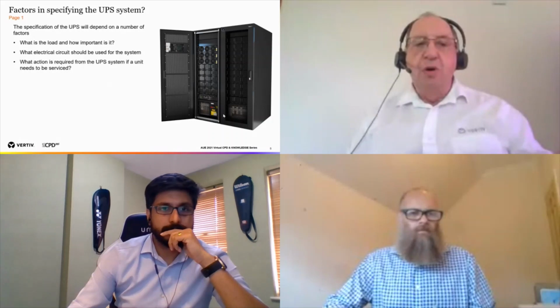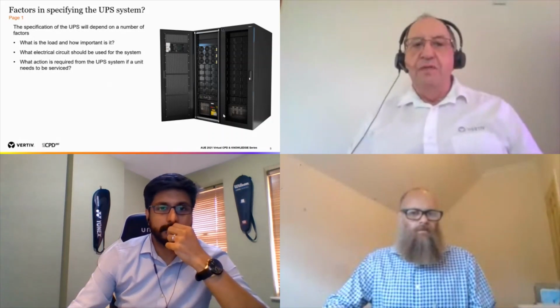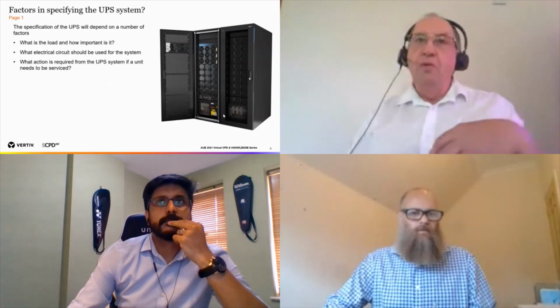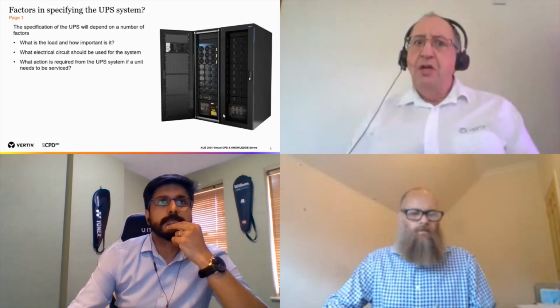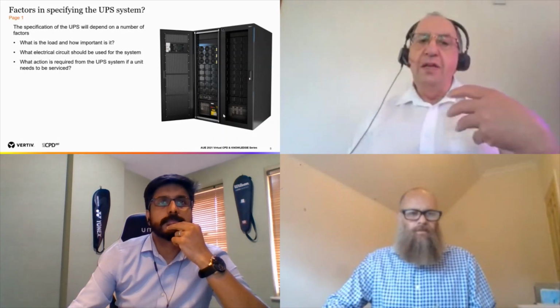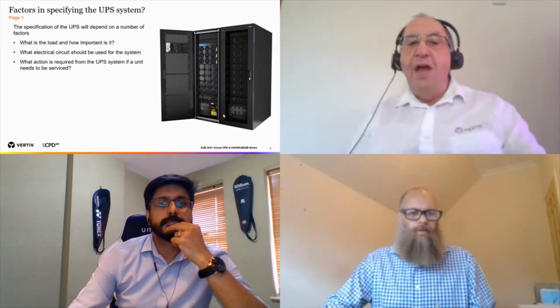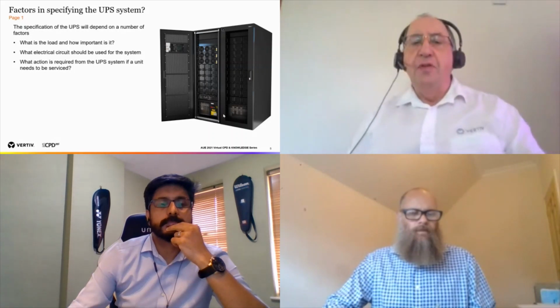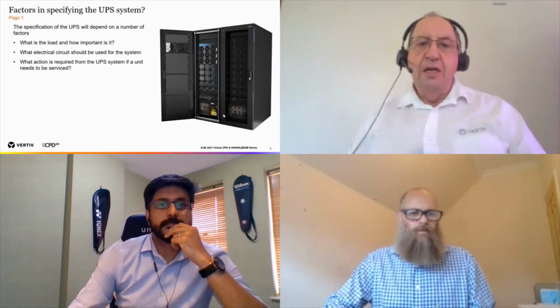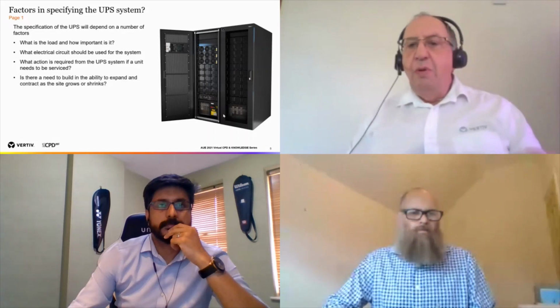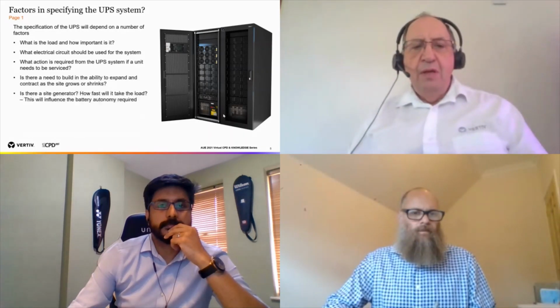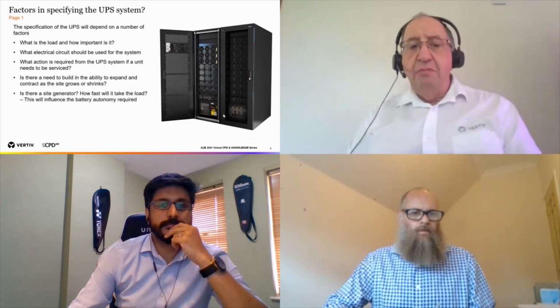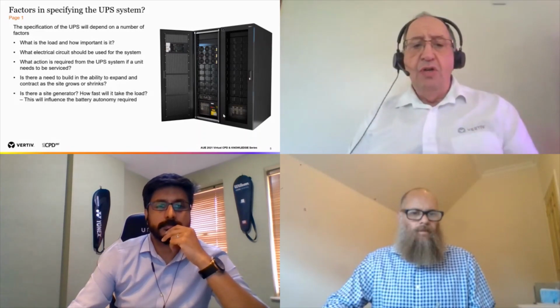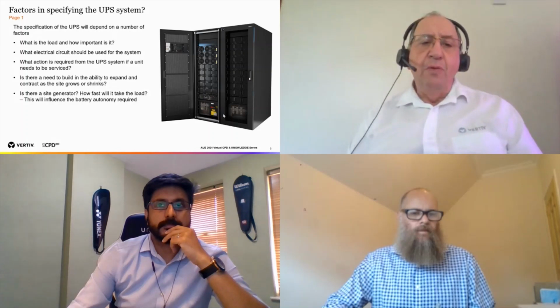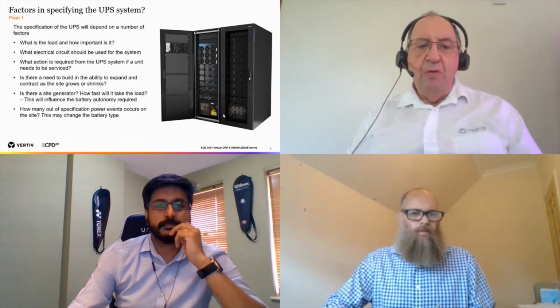What action is required if the unit needs to be serviced? In other words, do we want the local staff to react, or do we want the system to go off to the vendor to tell the vendor that the UPS needs something doing? Do we want the ability to expand and contract? Is there a site generator? How fast will it take the load? And obviously that will influence the battery autonomy required.